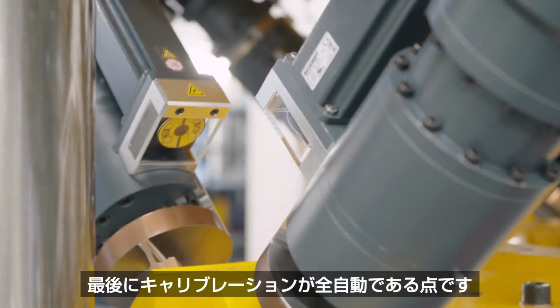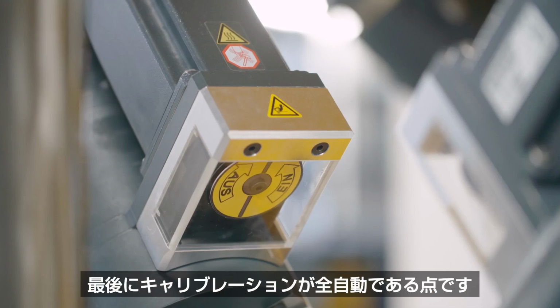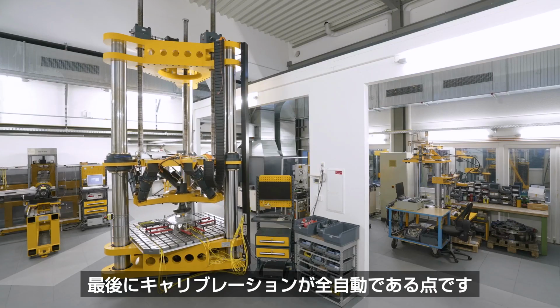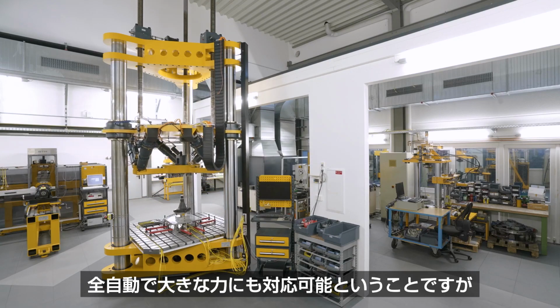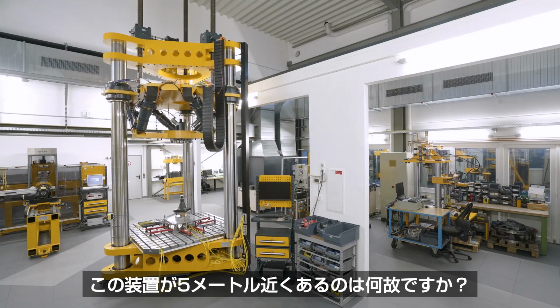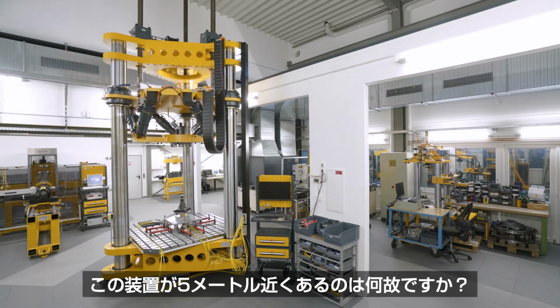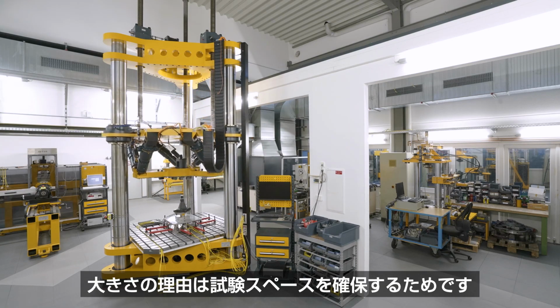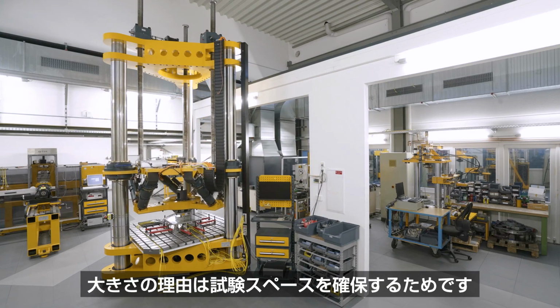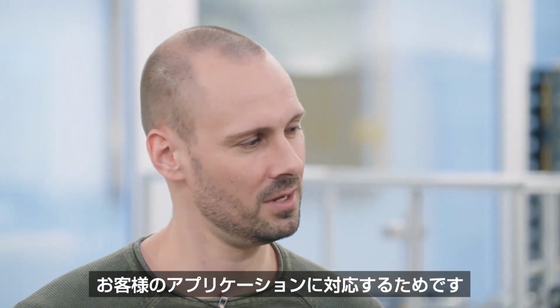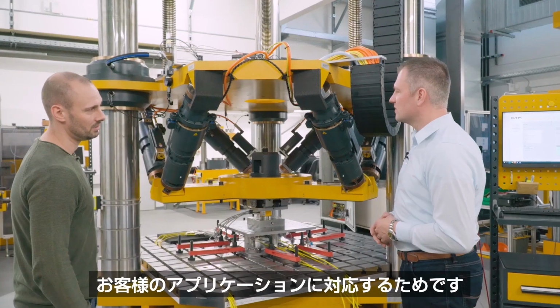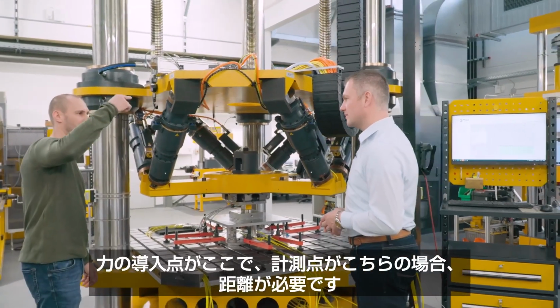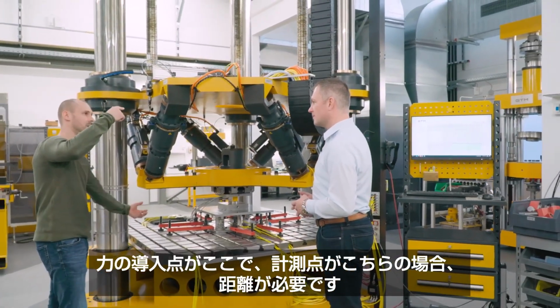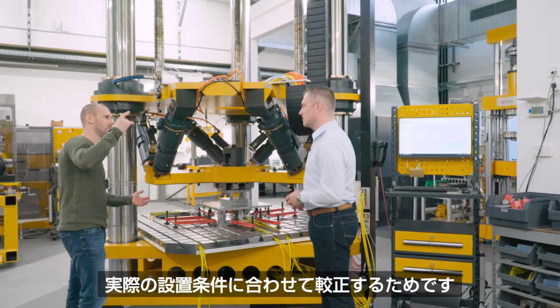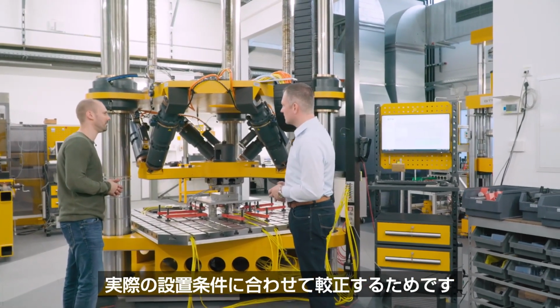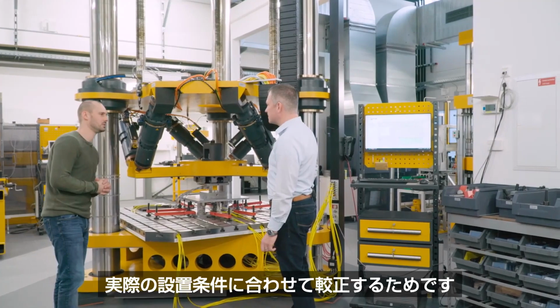And the last thing is the calibration itself. It's fully automatic. So fully automatic process and high forces, but why is this machine around 5 meters? What makes it big? The reason is that the testing space has to be so big because of the customer's applications. If the customer wants to have the introduction point of the force here and wants to measure here, he needs a lever arm. That's why we want to calibrate under realistic installation conditions.